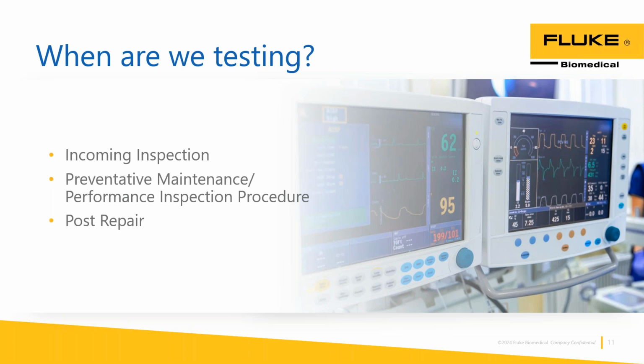And also with your incoming inspection, take a look to make sure that the electrical safety settings you're going to be using aren't different, or a different standard, for the incoming inspection itself, rather than when you do a preventative maintenance or post-repair check.